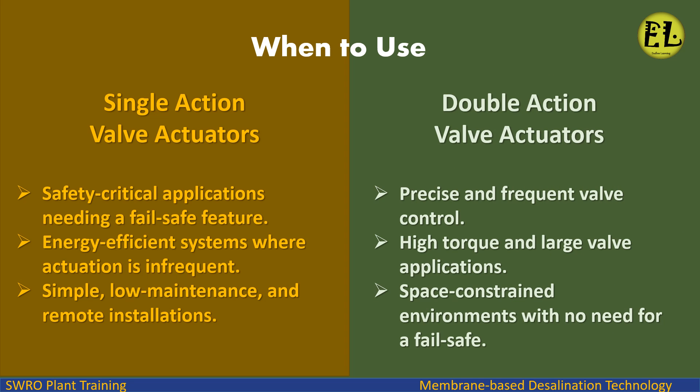When to use single action valve actuators: safety critical applications needing a fail safe feature, energy efficient systems where actuation is infrequent, simple low maintenance, and remote installations. Double action valve actuators: precise and frequent valve control, high torque and large valve applications, and space constrained environments with no need for a fail safe.